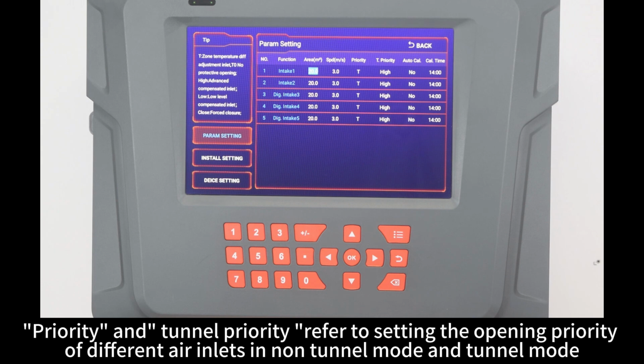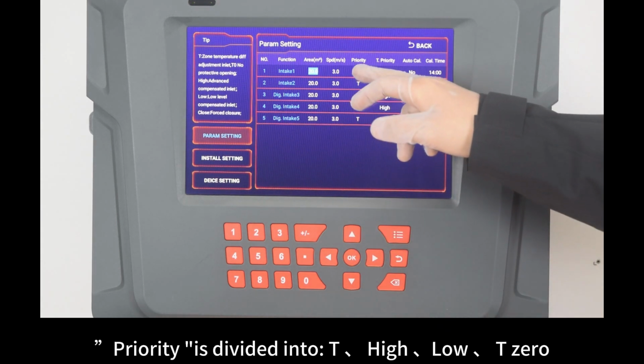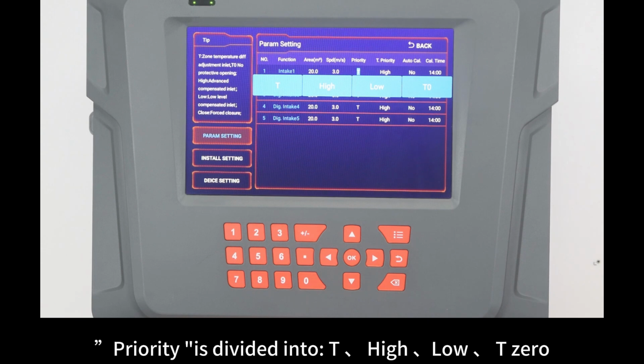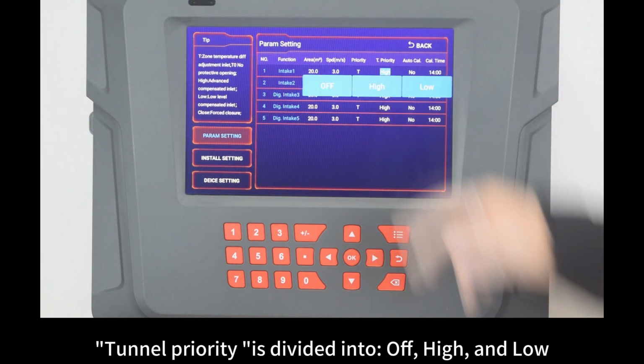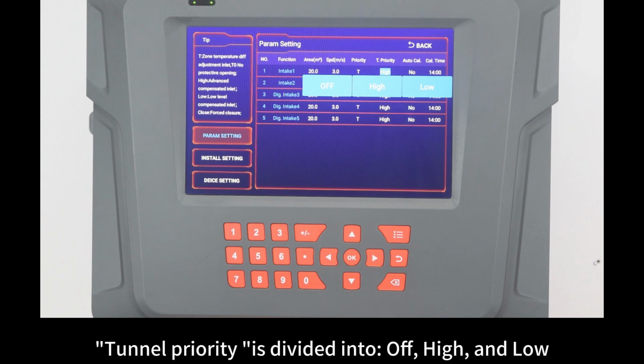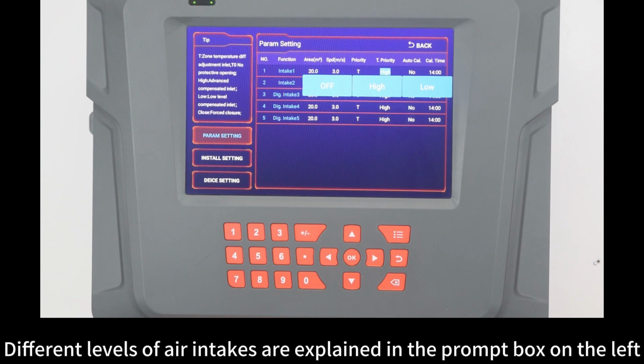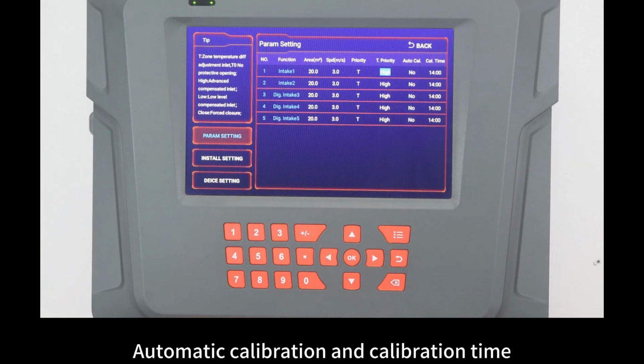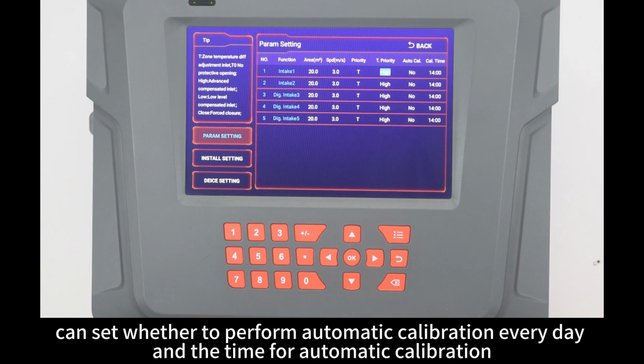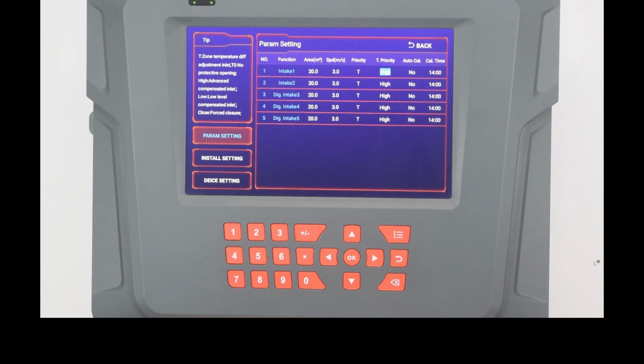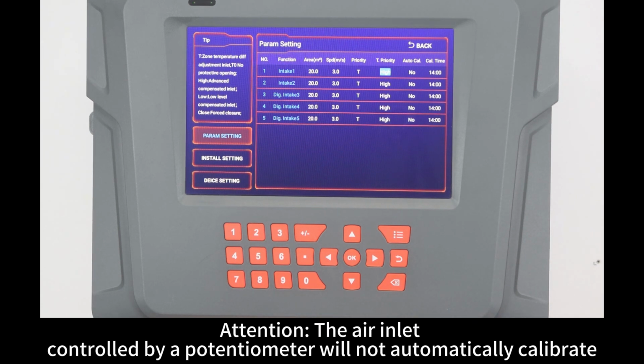Priority and tunnel priority refer to setting the opening priority of different air inlets in non-tunnel mode and tunnel mode. Priority is divided into T high-low, T0. Tunnel priority is divided into off, high, and low. Different levels of air intakes are explained in the prompt box on the left. Automatic calibration and calibration time can set whether to perform automatic calibration every day and the time for automatic calibration. Attention, the air inlet controlled by a potentiometer will not automatically calibrate.